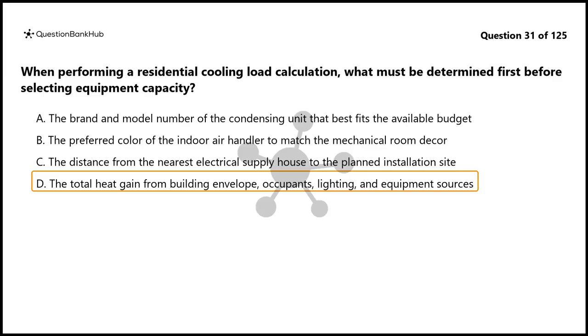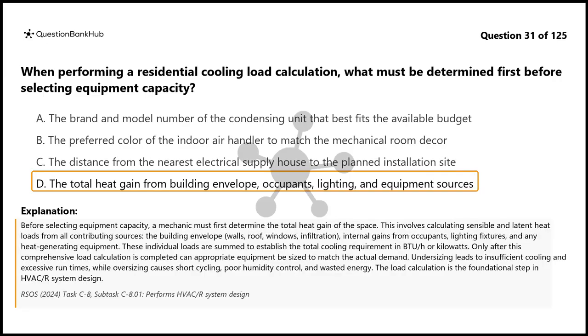The correct answer is D. Before selecting equipment capacity, a mechanic must first determine the total heat gain of the space. This involves calculating sensible and latent heat loads from all contributing sources, the building envelope, walls, roof, windows, infiltration, internal gains from occupants, lighting fixtures, and any heat-generating equipment.